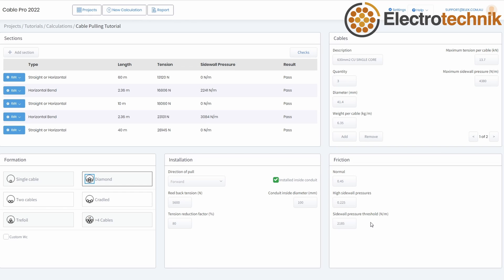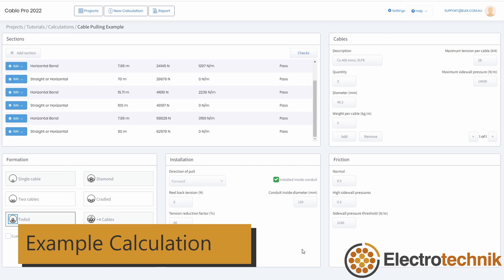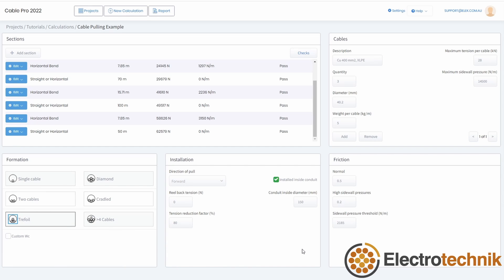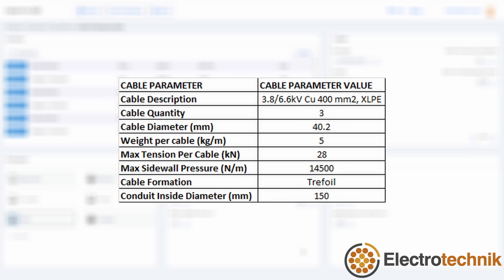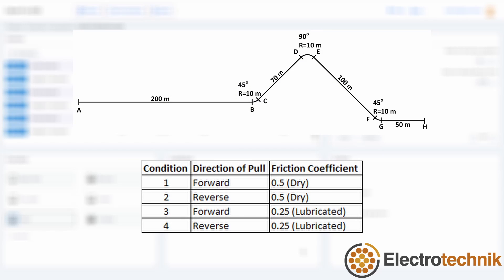Now that you've been familiarised with each of the input sections of the calculator, it's time to show you an example calculation. The cable we're going to be pulling is a 400mm² copper cable with XLPE insulation. First, we should take a look at the section inputs. Currently displayed on screen is the diagram we will be using, along with the table denoting the section inputs. Next, it's important to enter the specifics of the cable. The table currently displayed on screen shows the values of the copper cable for this calculation. Feel free to pause the video if you wish to enter these values yourself.